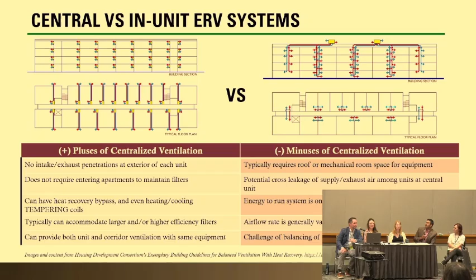So what this system resulted in, once the decision was adopted to go central, for the main reasons of minimizing penetrations, and the other big one was getting a piece of equipment that can meet passive house level energy efficiency, which was very hard to find in the smaller ERVs at least at that time. The technology has been evolving and getting better. Once that decision was made, finding a place for all the ductwork that minimized things like fire smoke dampers and other considerations ended up being quite intense on the top floor.